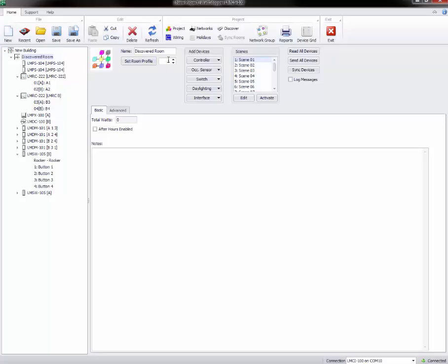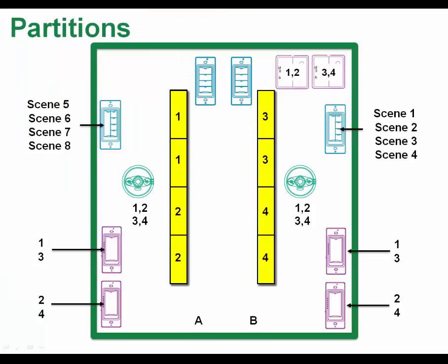If we start activating walls, LMCS will pick up on that and will automatically change the profile number. However, my buttons are currently deactivated, so I'm left in profile 1. You can manually switch it by clicking on set profile, and then you can scroll through, you can see you've got the 16 scenes. I'm going to leave it in 1 now because we're going to set our space up just like that.